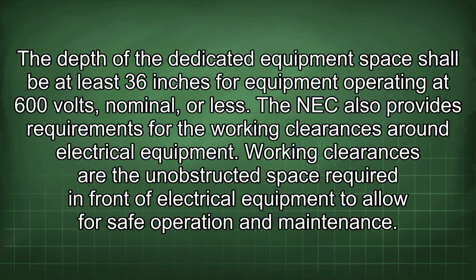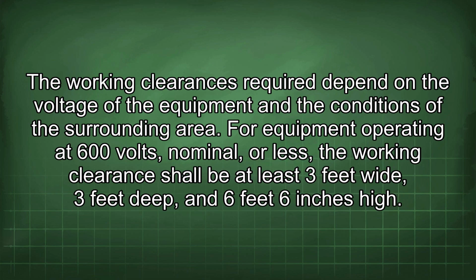The NEC also provides requirements for the working clearances around electrical equipment. Working clearances are the unobstructed space required in front of electrical equipment to allow for safe operation and maintenance. The working clearances required depend on the voltage of the equipment and the conditions of the surrounding area. For equipment operating at 600 volts, nominal or less, the working clearance shall be at least 3 feet wide, 3 feet deep, and 6 feet 6 inches high.